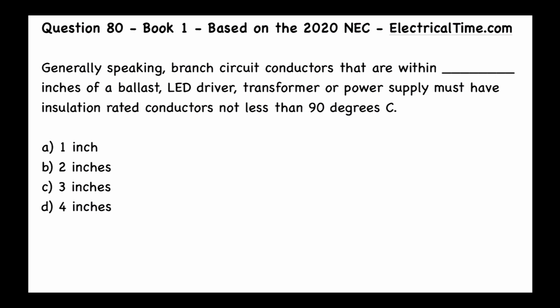Generally speaking, branch circuit conductors that are within blank inches of a ballast, LED driver, transformer, or power supply must have insulation rated conductors not less than 90 degrees C. The first answer is A, 1 inch, B, 2 inches, C, 3 inches, or D, 4 inches.